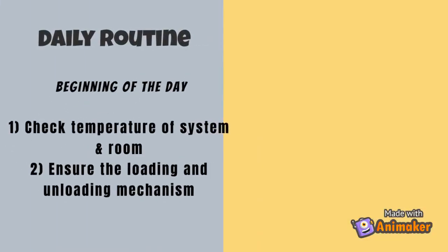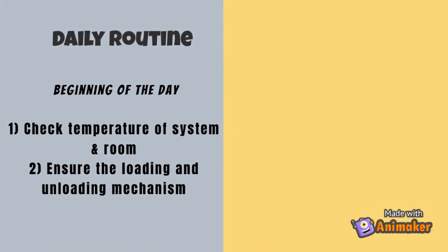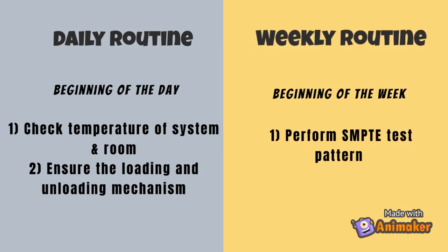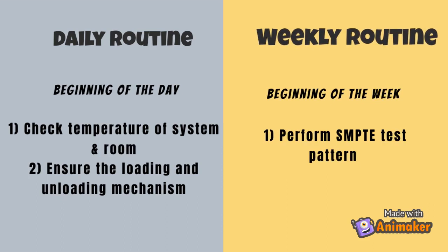The quality assurance of the CR reader can be conducted in several ways. For the daily routine, what we can do is check the temperature of the CR system and room. Moreover, we also ensure the image reader loading and unloading mechanism is properly functional.